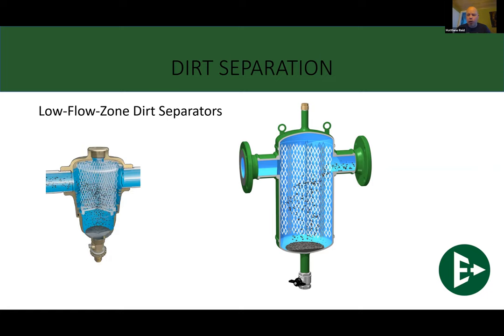There are other ways for oxygen to get inside of a system. And once that happens, then you get right back to that oxidization of ferrous metals inside the system. You're going to have dirt creation. You're going to need some way to get that dirt back out of the system. So food for thought, if you're not using a dirt separator or something right now to catch that dirt, it might be something you want to consider moving forward.